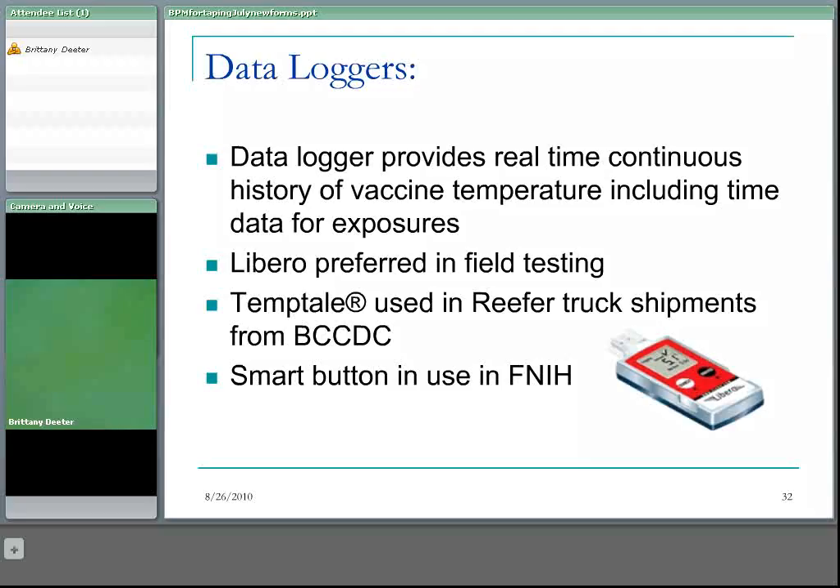Data loggers provide real-time continuous history of vaccine temperature, including time data for exposures — essentially a map of all temperatures the vaccine has been exposed to and for how long. The Libero was preferred in recent field testing: it has a USB port that can be downloaded in the field and interpreted by a biological product consultant, the analysis software is free and automatically generates a report, and it is accurate to plus or minus 0.2 degrees. With Temptale, used in reefer truck shipments from the BCCDC pharmacy, the USB cannot be downloaded in the field and must be shipped back to the pharmacy for determinations.